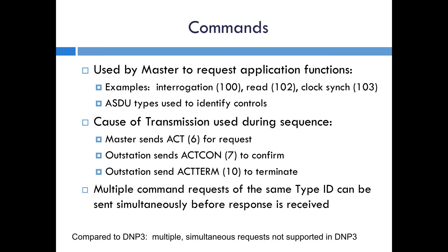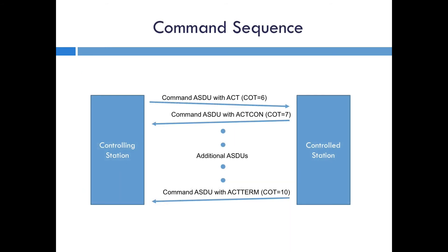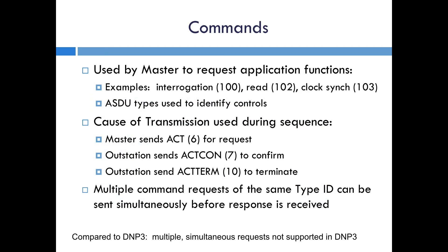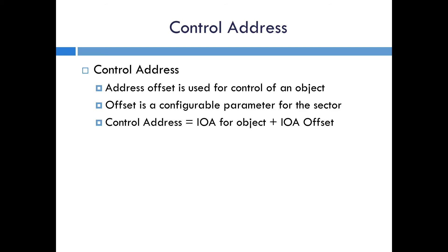The specification also describes controls. This is basically where the master is making a request for one of these application functions — interrogation, read, or sending a command — and it uses the ASDU type to identify what type of control it is. It also uses a few of the cause of transmissions: when the master sends a request it sends an activation of COT 6, when the outstation sends back a confirmation it's the ACT-CON which is COT 7, and then the outstation can send an ACT-TERM — COT 10 — to terminate that control. Also note that the specification allows multiple command requests of the same type ID to be sent simultaneously before a response is received, in contrast to DNP3 in which multiple simultaneous requests are not supported.